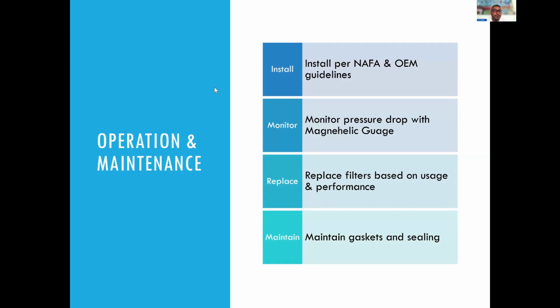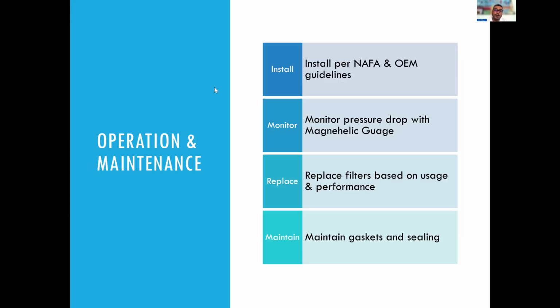For monitoring, use a functioning Magnehelic gauge. I think we've all been to a site and asked, how are you figuring out when you're going to change your filters? And they say, well, the Magnehelic doesn't work. Well, that makes it hard to figure out when you're supposed to change your filters, because all you're doing now is opening the door and seeing if they're dirty or not. Magnehelics play a very critical role in knowing the pressure drop and knowing when to actually change the filter.